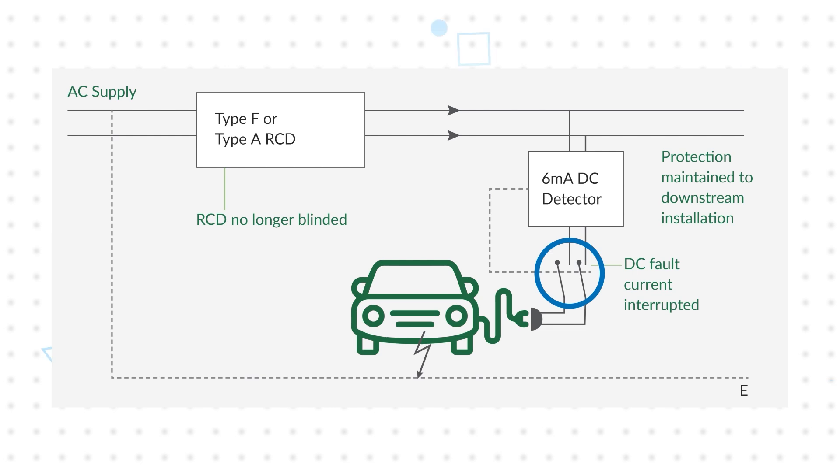Littelfuse RCM monitors can be placed in series to monitor for DC currents. If a DC current of 6 milliamps or higher is detected, the monitor drives its fault output high, which activates a contactor or circuit breaker to disconnect the EV, ensuring the safety and integrity of the AC installation.